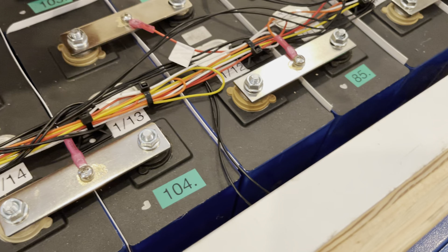As I started to loosen the nuts, I turned off the charger and put the BMS in sleep mode. And as I started to loosen the nuts, I discovered that nut right there on the bus bar between cell 11 and 12 had never been tightened. That's what was causing all the issues.